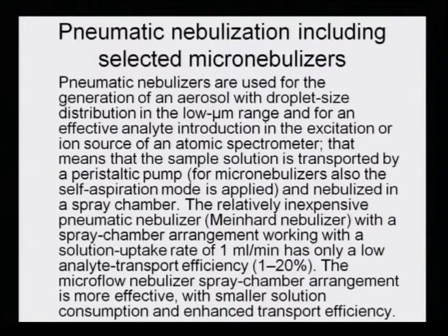So, what is the advantage? The advantage is that with these microflow nebulizers, not too much solution is coming. As a result, there is an efficiency of forming the aerosol in a smaller droplet size, and the droplets are sufficiently large in number to be analyzed properly.